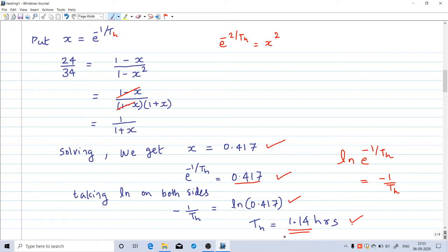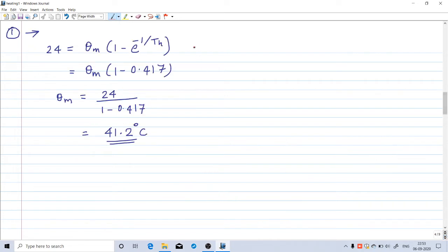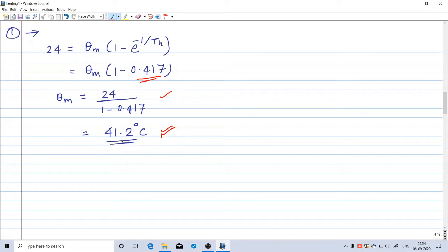Now we calculate the final steady temperature rise theta_m by substituting th into equation 1: 24 equals theta_m into (1 minus e raised to minus 1 by th). We know e raised to minus 1 by th equals 0.417, so substituting gives theta_m equal to 41.2 degrees Celsius. This is the final steady temperature rise. We have now calculated both th equal to 1.14 hours and theta_m equal to 41.2 degrees Celsius.